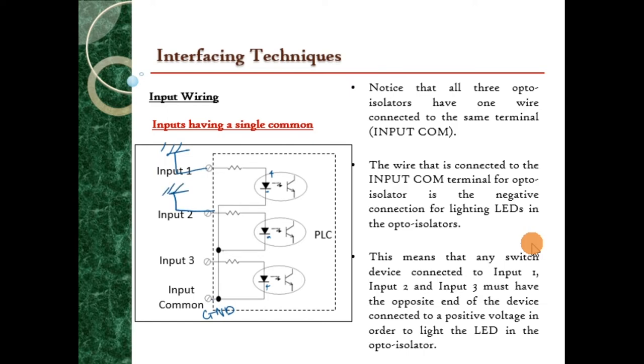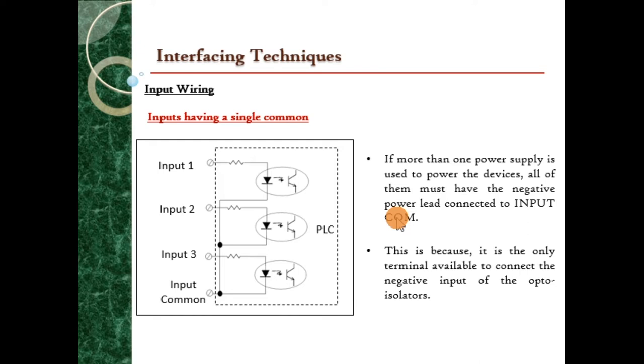Okay, the positive voltage goes on the opposite side of this device. If more than one power supply is used to power the devices, all of them must have the negative power lead connected to input COM. So meaning that if these devices are connected to different power sources, for example, input 1 is connected to 12 volt, input 2 is connected to 24 volt, and input 3 is connected to 5 volt, so it has three different input sources, then the other end of this circuit must be connected to a common ground here.